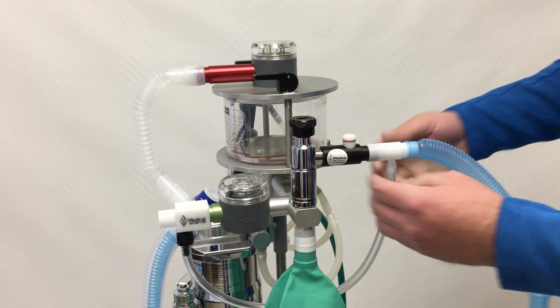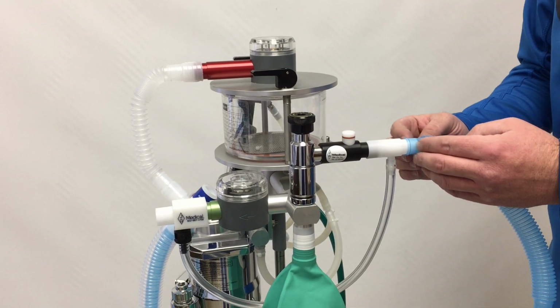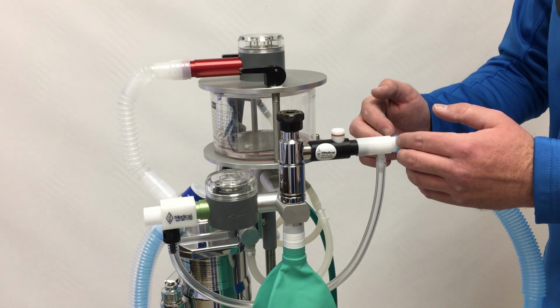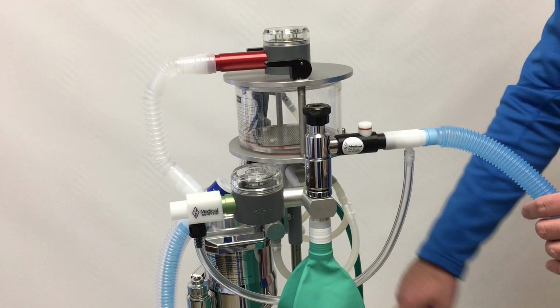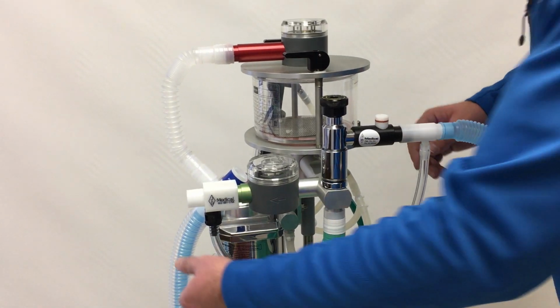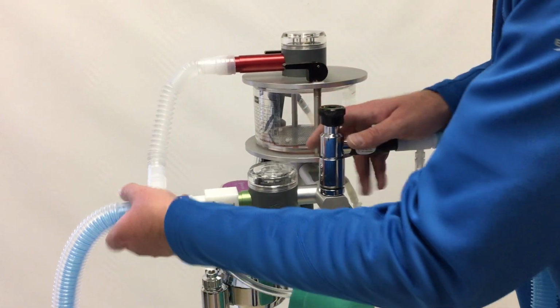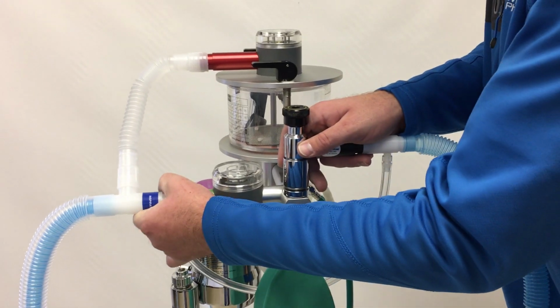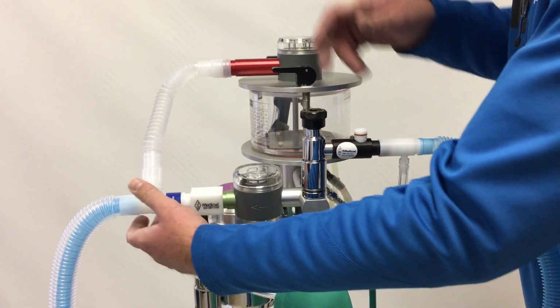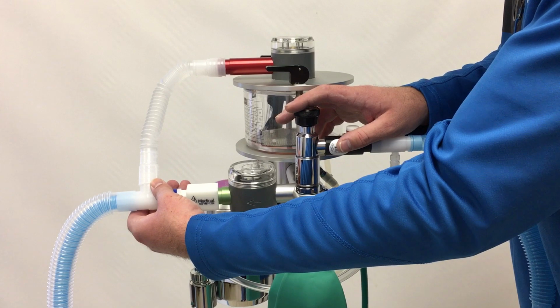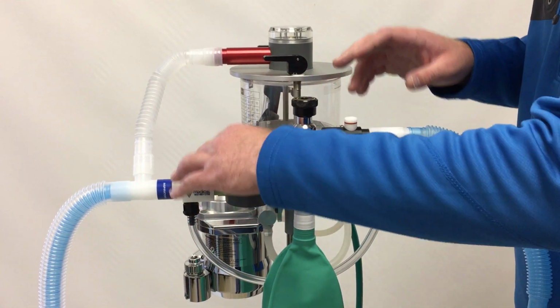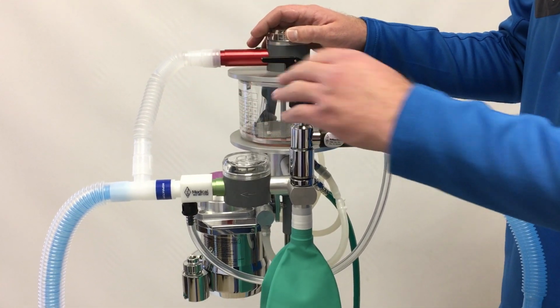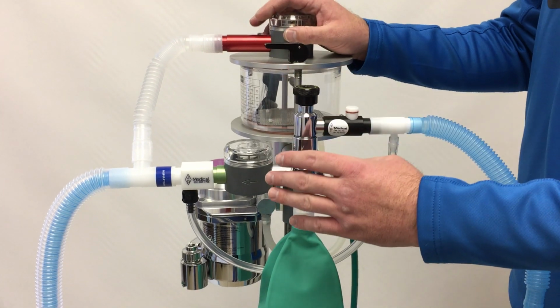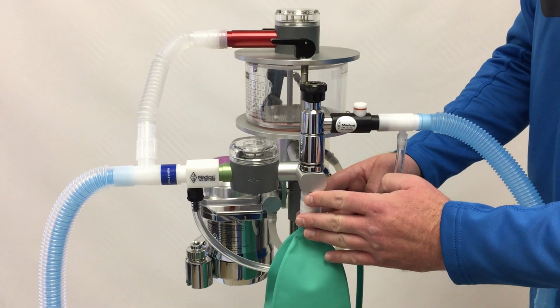So it should be the ultimate exhaust of the anesthesia machine coming in last to the exhaust, which will then exhaust out into the scavenger system of the facility. So insert the valve, give it a good twist for snug, and reconnect the patient circuit. Again, it can be connected to the expiratory valve if it's closer to the pop-off valve.